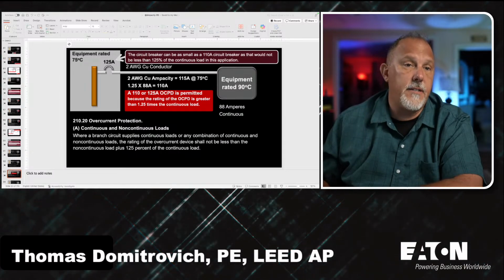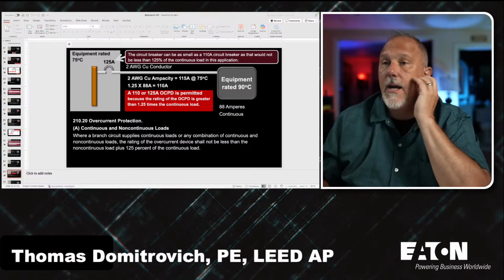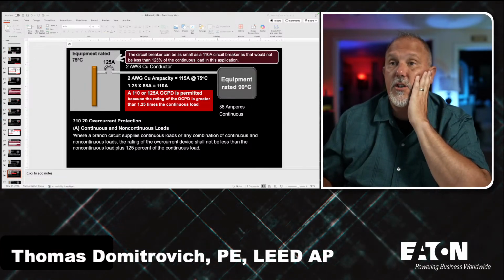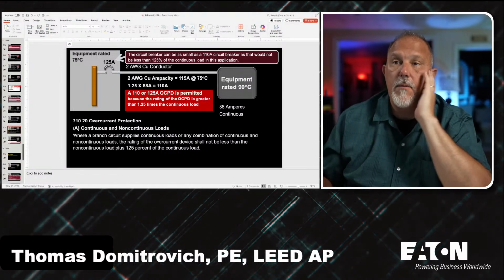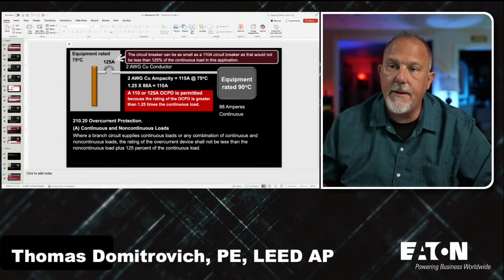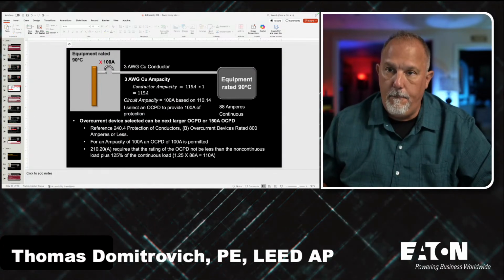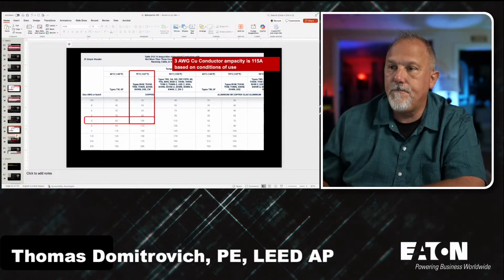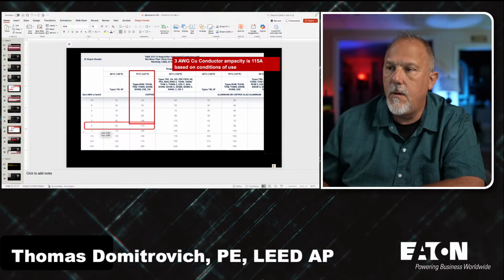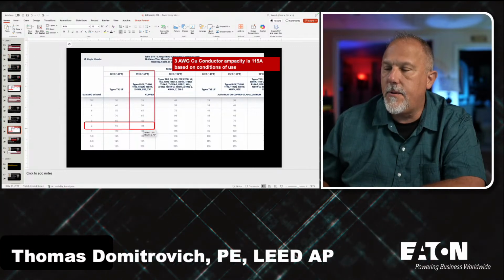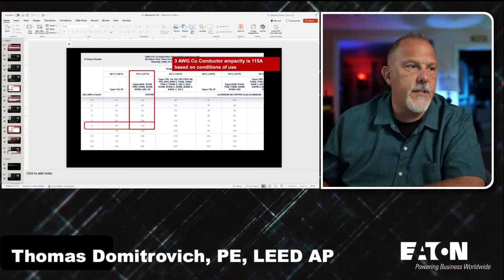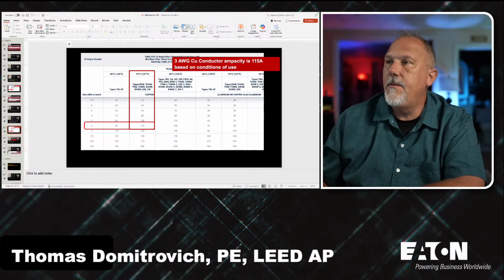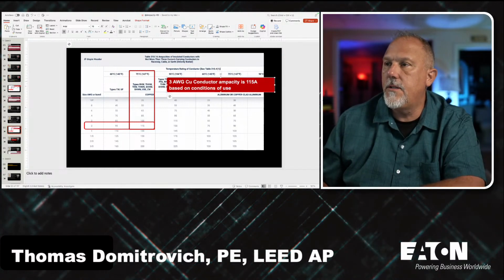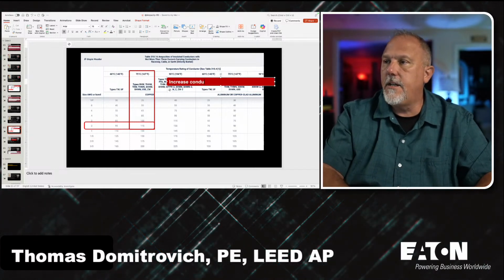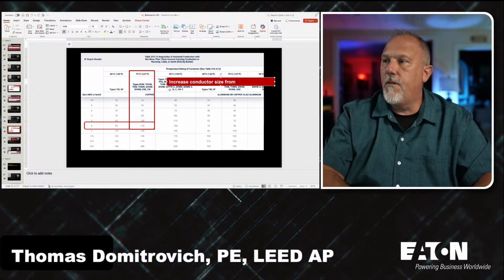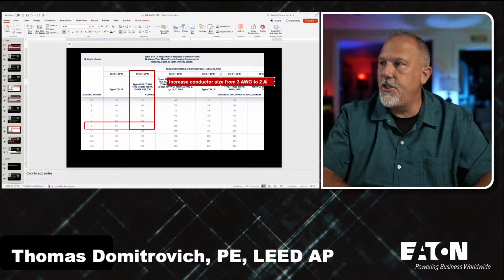I need to increase the conductor size. That's what I need to do. Let me grab this slide. Let me put this in here. If I can't use this one, I could go to a number 2. I can increase the conductor size. Increase conductor size from 3 gauge to 2 gauge.